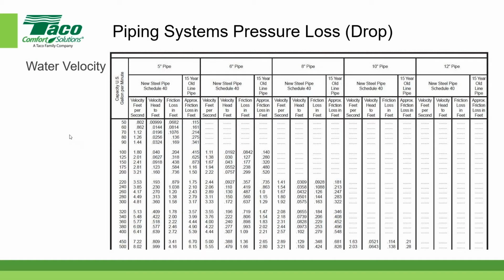We have another question. Is there a reference to maximum feet per second for certain pipe sizes? Yeah, actually, I have some guidelines as we go through this presentation. Most people design hydronic systems for a velocity range somewhere between 6 to 10 feet per second, and most will design for pipe velocities of less than 8 feet per second. That's probably the most common for hydronic heating and cooling systems. Plumbing systems generally use a much lower velocity, but for standard HVAC heating and cooling systems, less than 8 feet per second is the most common value.